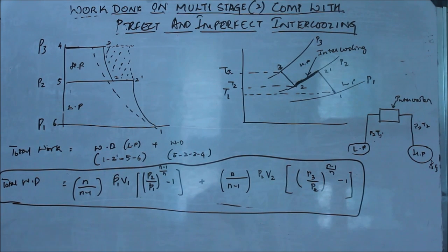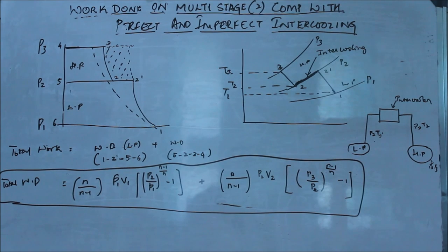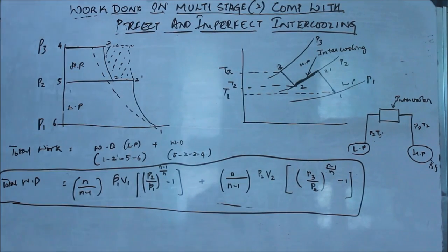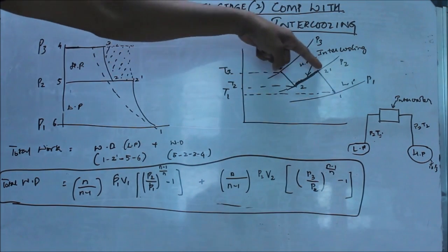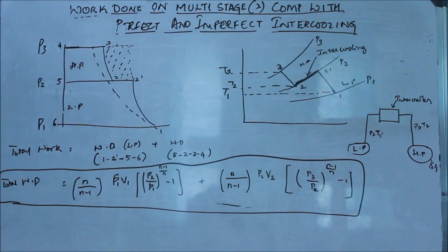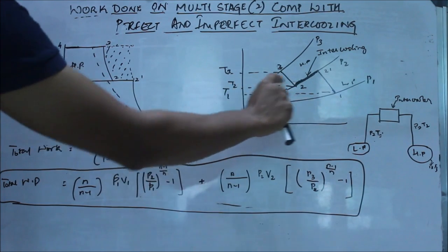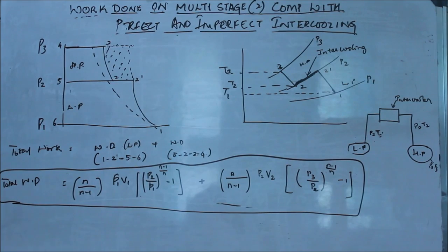First I will talk about imperfect intercooling. What happens in imperfect intercooling is that the temperature T2 that comes out of the low pressure cylinder after the first stage of compression and passes through the intercooler will not get cooled to the initial temperature T1. So if we look at this TS graph, we can see that after low pressure compression, the temperature rises from 1 to 2' and then it passes through the intercooling phase. This line here is the intercooler where the temperature reduces, but it does not reduce to T1. So T2 is not equal to T1 — this type of cooling is called imperfect intercooling. Then it gets again compressed in the high pressure cylinder and its temperature rises to T3.